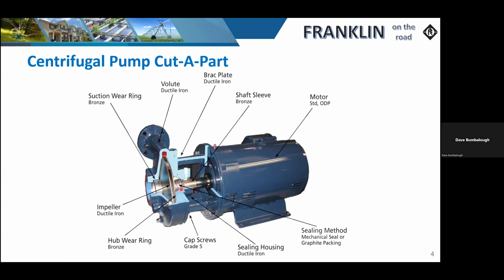There are two things you've got to be cautious of when dealing with a pump. The first is that every pump out there, unless it's a submersible, of course, you have to prime it. You have to add water to it. These seals are compressed seals, and if they are run for any moment of time dry, they could get damaged due to friction. So you've got to be very careful there.